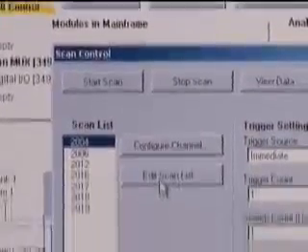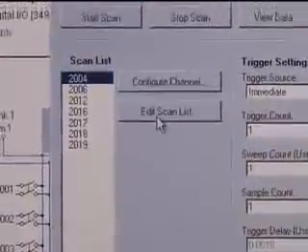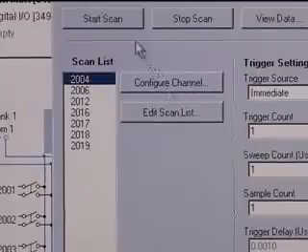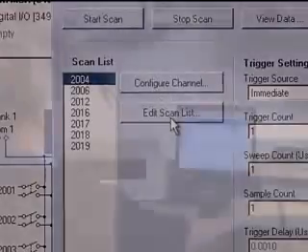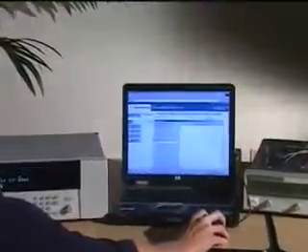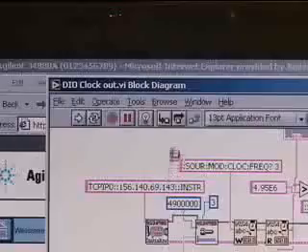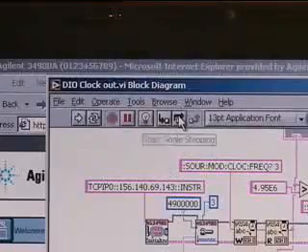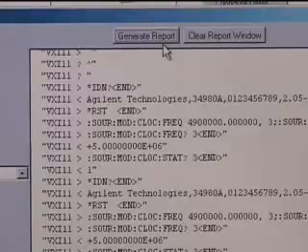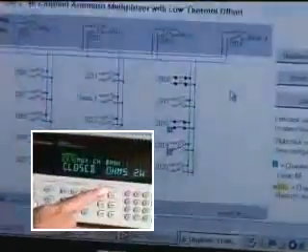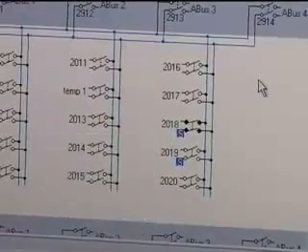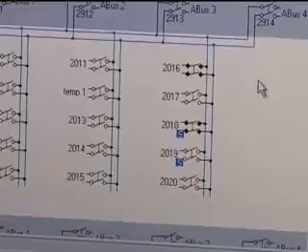You can also use the web interface to automate the measurements by setting up a scan. Simply select the channels you want to include in the scan and a delay between readings and scans. The web interface is an incredible diagnostic tool. It can capture the SCPI code sent to the instrument and show the real-time state of any channel. For relay maintenance, you can also see the number of closed cycles for the life of each relay. Being LAN-based, the web interface is easily accessed remotely.